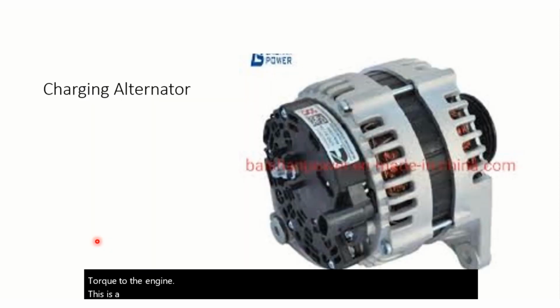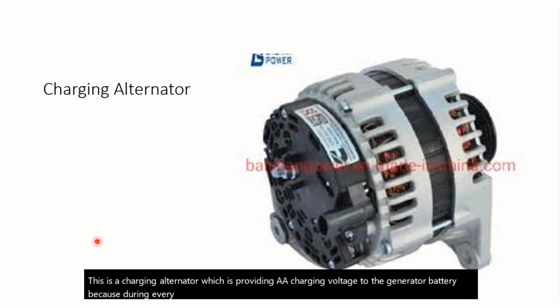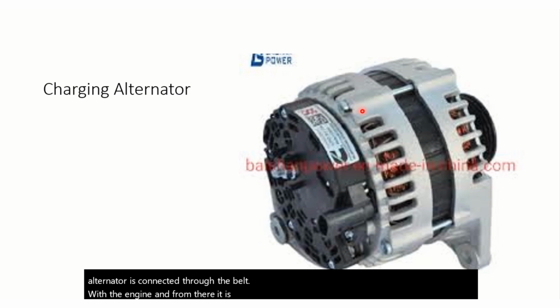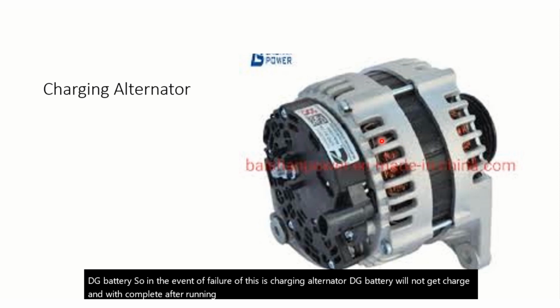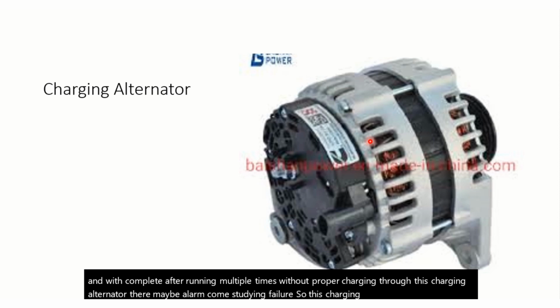This is a charging alternator, which provides a charging voltage to the generator battery, because during every crank a huge amount of current is drawn from the battery, so we lose capacity every time cranking takes place. To replenish the battery with the charge we have used, we use this charging alternator. It is connected through a belt with the engine, and from there it runs and produces output, and this output is directly connected to the DG battery. In the event of failure of this charging alternator, the DG battery will not get charged, and after running multiple times without proper charging, a starting failure alarm may come. So this charging alternator and battery charger are very essential components to ensure the health of the battery all the time.